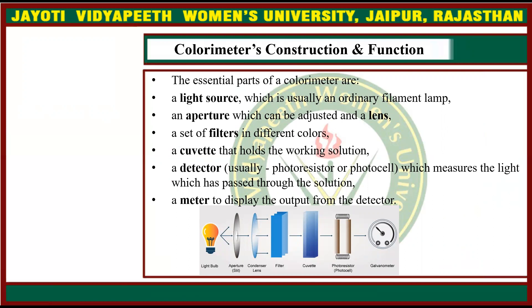The essential parts of the colorimeter are: first, a light source, which is usually an ordinary filament lamp; an aperture which can be adjusted, and a lens; a set of filters in different colors; a cuvette that holds the working solution; and a detector, usually a photoresistor or photocell, which measures the light that has passed through the solution, and a meter to display the output from the detector.